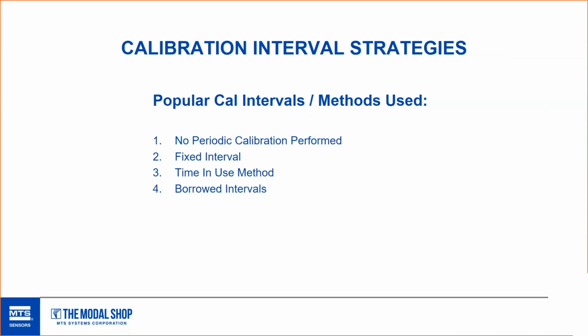Borrowed intervals: this one sounds too good to be true. Borrowing sensors that have been calibrated on a similar or acceptable method that fits your testing. Risk tolerances must be agreed upon, but it really can be an effective cal approach. Another example can be sensors rented for a project. Assuming your rental partner is reputable, the calibration challenge is already solved.